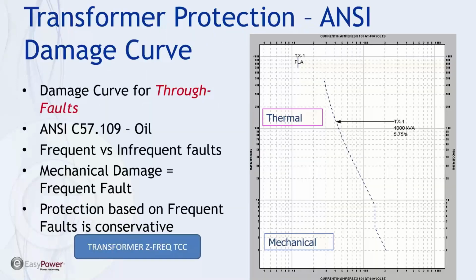Now this again makes more sense when we look at the protection curves, or the TCC curves. So this is a typical damage curve, and again what we would do is predict the current at an individual downstream bus, and that tells us whether or not it's going to intersect the damage curve of the transformer. This plot is based on an ANSI C57.109 oil rated transformer of 1000 kVA with an impedance of 5.75%. Again, this is all information that's entered during data collection, so it's important to get the data accurate when we're doing data collection.